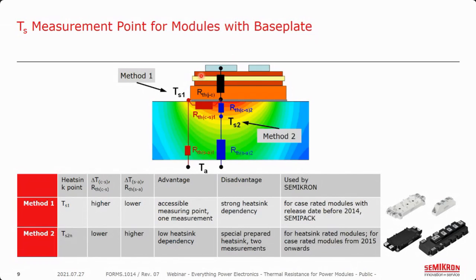Following up on that: when looking at the chips for measurements, do you consider heat flow in or out of the terminals and bus bars? The short answer is that we don't. Undoubtedly there is some heat flow, but in most high-power converters it's inconsequential compared with the amount of heat flowing out through the base of the device. That's the way these linear thermal models are made — the assumption is that heat is flowing out through the base of the device.